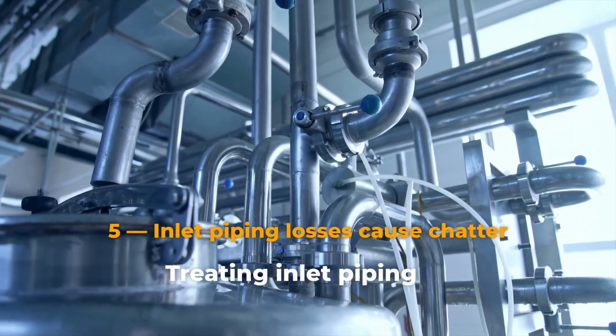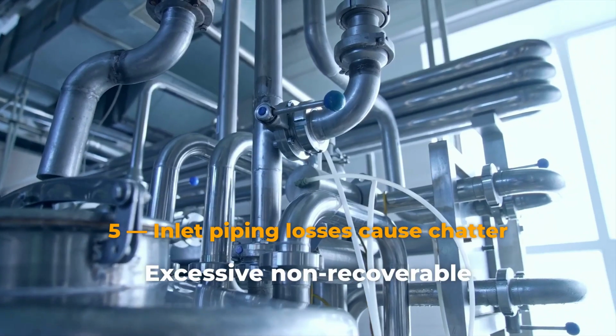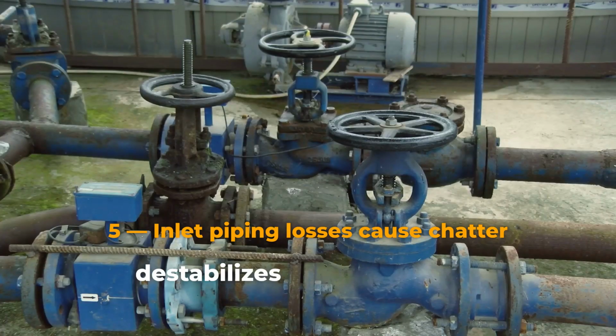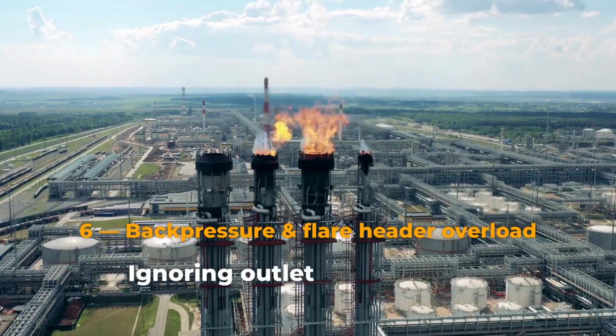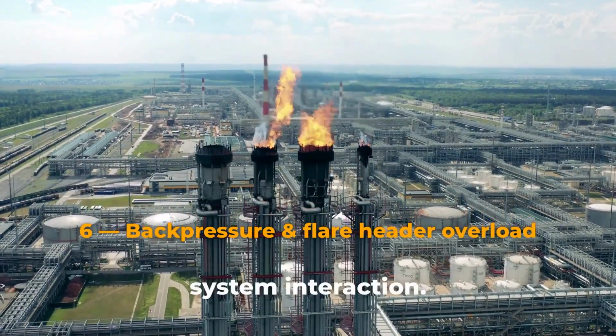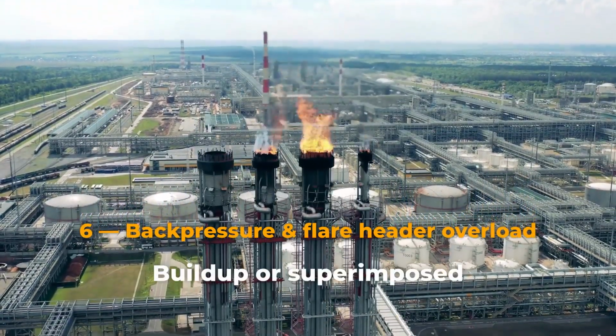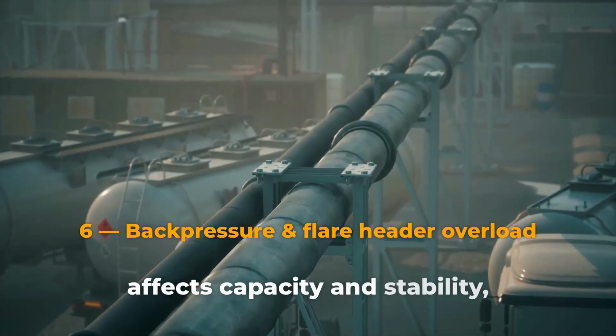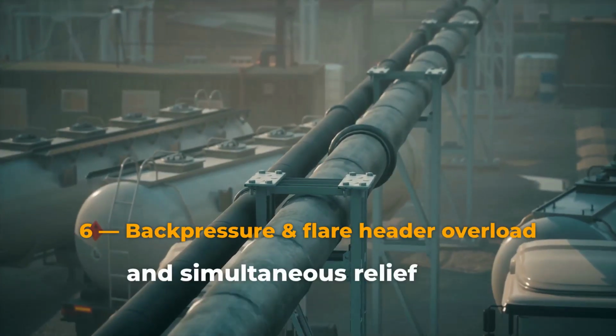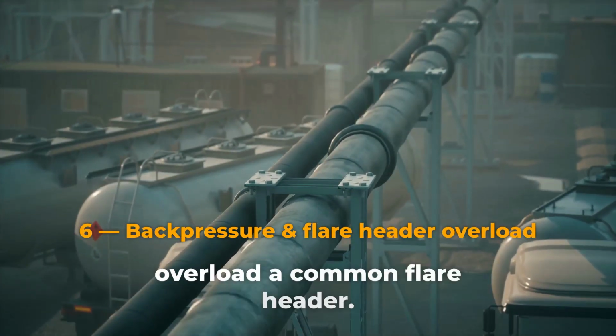Treating inlet piping as harmless. Excessive non-recoverable inlet load destabilizes a spring-loaded valve and contributes to chatter. Ignoring outlet back pressure and disposal system interaction. Build-up or superimposed back pressure affects capacity and stability, and simultaneous relief loads can overload a common flare header.